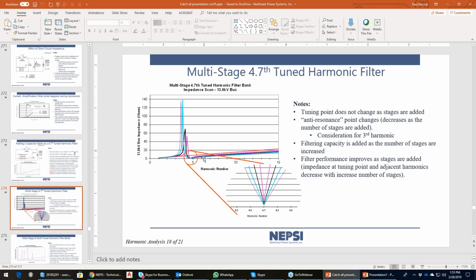The reactive power output of the filter is usually desirable. That's why you're installing the filter bank in the first place. But the secondary benefit, and sometimes it's a primary benefit, is that you're looking to filter harmonic current from the system. A capacitor bank won't do that, a filter bank will. So there are additional benefits related to a harmonic filter. It is also worth pointing out that sometimes there are concerns about transients in the network during switching. A harmonic filter actually eliminates that transient concern also. So it's a third benefit that you get from harmonic filters. So, next question.